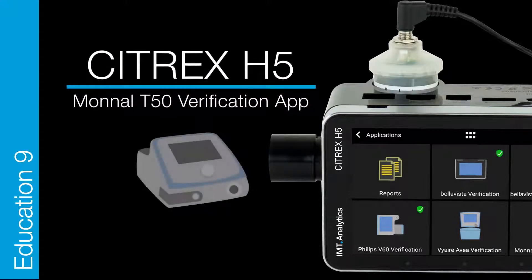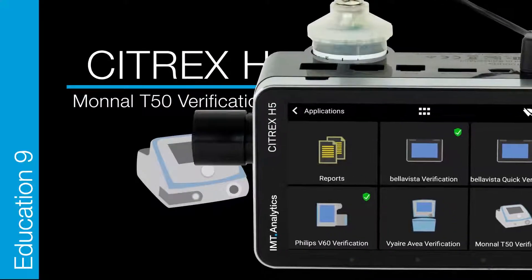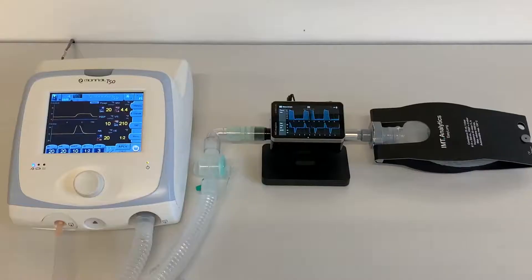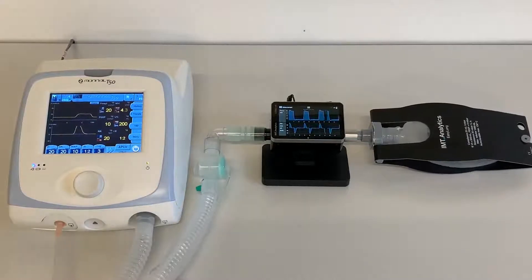Citrex H5 Education — Monnal T50 from Air Liquide Medical Systems. Let's start. First, set up the Monnal T50 ventilator, Citrex H5 gas flow analyzer, and a test lung.